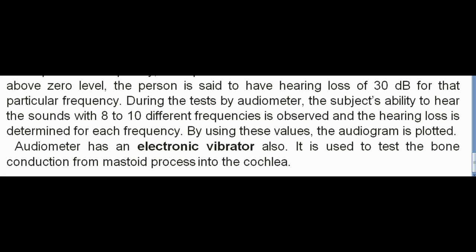During tests by audiometer, the subject's ability to hear sounds at 8 to 10 different frequencies is observed and the hearing loss is determined for each frequency. Using these values, the audiogram is plotted. The audiometer also has an electronic vibrator, which is used to test bone conduction from the mastoid process into the cochlea.